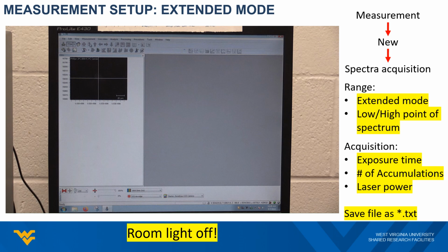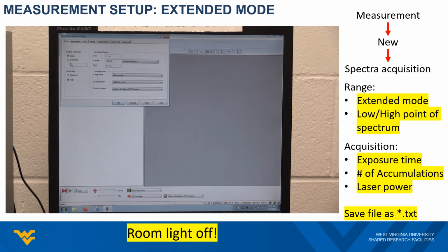The measurement setup starts from the Measurement tab, then New, then Spectral Acquisition. This will bring you to a Spectral Acquisition setup window. Under the Range tab, you could choose between 2 measurement modes, the static mode and the extended mode. The major difference between these 2 modes is the spectral range you could achieve. When choosing extended mode, you could determine the low and high wave number settings of the measurement, which is from 100 inverse centimeter minimum to 3,200 inverse centimeter maximum.